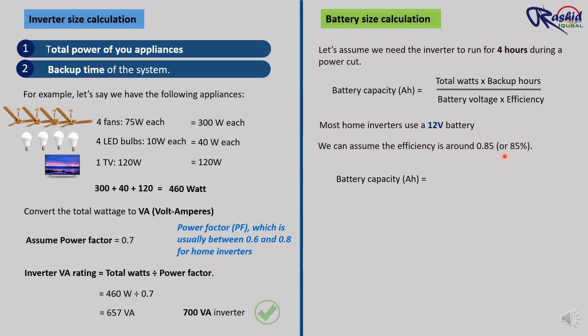So let's plug in the values. Battery capacity equals 460 watts multiplied by 4 hours, divided by 12 volts multiplied by 0.85. After multiplication it becomes 1840 divided by 10.2. After dividing this value we get 180.39 Ah. This is the battery capacity which we require.